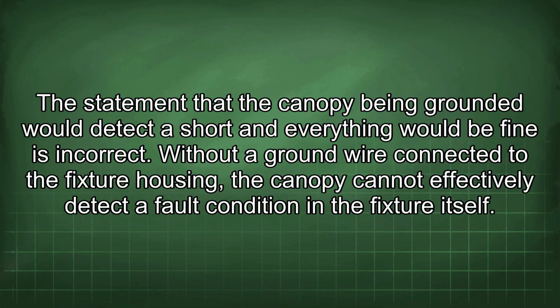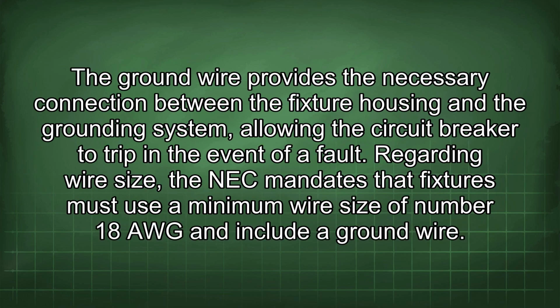The statement that the canopy being grounded would detect a short and everything would be fine is incorrect. Without a ground wire connected to the fixture housing, the canopy cannot effectively detect a fault condition in the fixture itself. The ground wire provides the necessary connection between the fixture housing and the grounding system, allowing the circuit breaker to trip in the event of a fault.